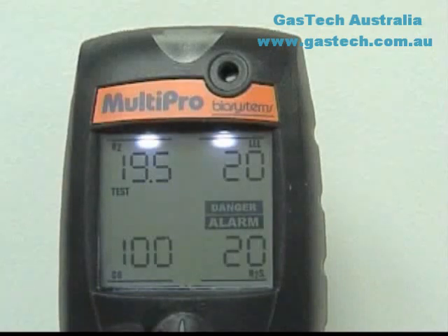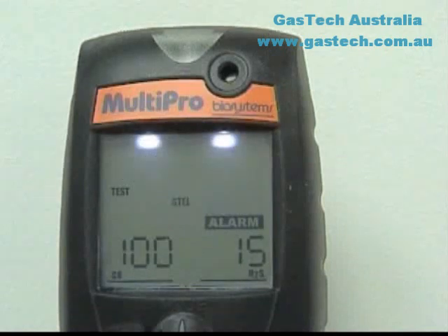Danger alarms indicate a significantly hazardous condition. The danger alarm condition is louder than the warning alarm and is dual tone. Short-term exposure limit, or STEL alarm values, represent the average concentration of instrument readings for the target gas for the most recently completed 15 minutes of operation. The default STEL alarm level for the Multipro CO sensor is 100 parts per million. The default STEL value for the Multipro's H2S sensor is 15 parts per million.